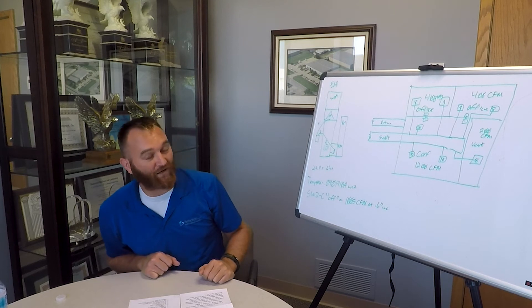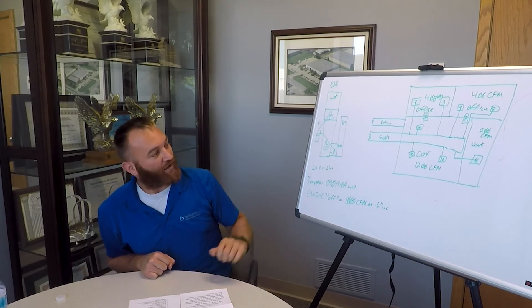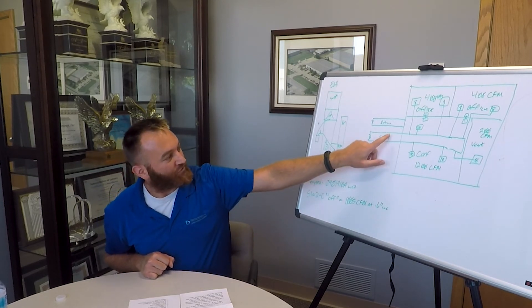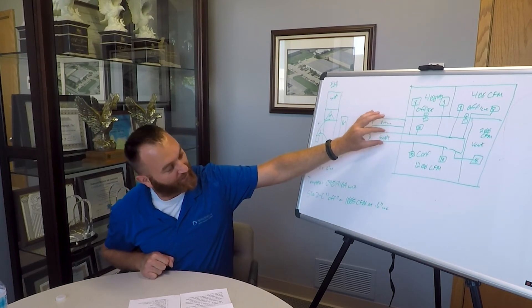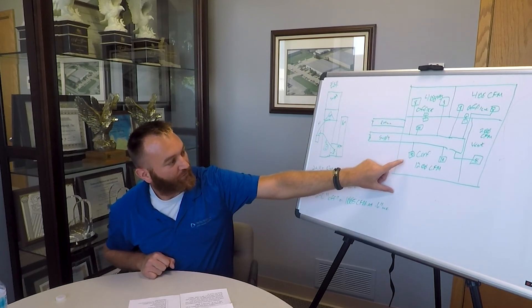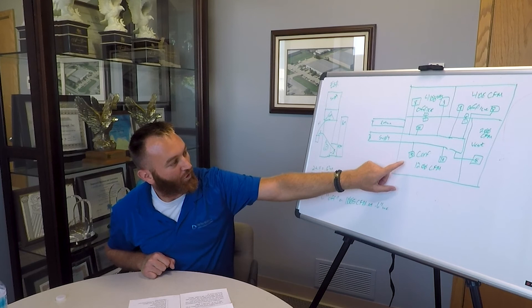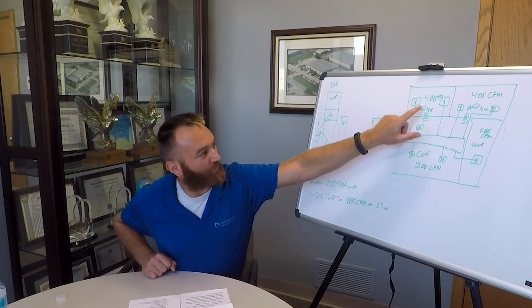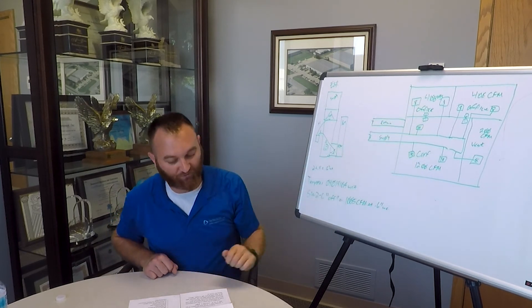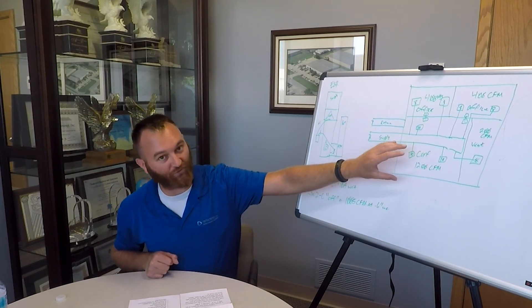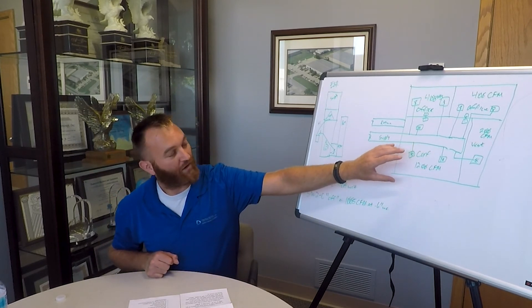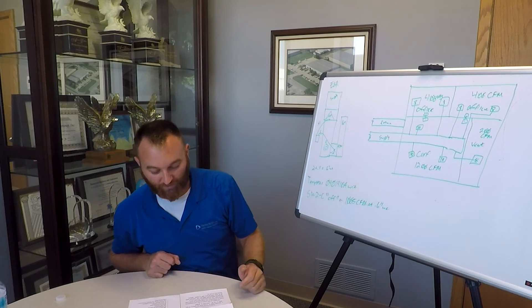You can use the static and velocity pressure readings with a pitot-static tube. You can traverse your ductwork to get your airflow in a run, or you can use a hood to measure the different supplies in each space. It's important that you have proper air balance so that each space is provided the proper CFM to heat or cool that space properly.